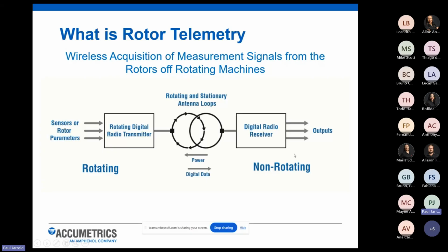The outputs can come in forms such as relay contacts, 4 to 20 current loop outputs, or a straight digital, like a Modbus TCP digital output. And then inside our radio receiver unit, we're creating an induction power signal that comes back the other way and goes across that same air gap from the stator now back to the rotor and powers our electronics out on the rotor. So all of our systems are completely independent and self-powered. We don't require battery power or power from the rotating shaft, like field voltage contact or anything like that. Completely independent system that's very robust and reliable.